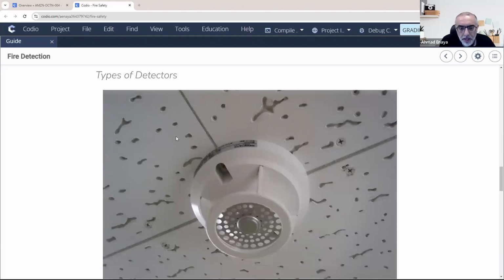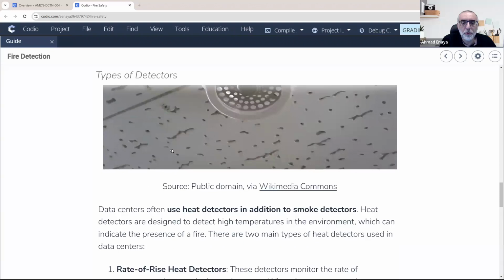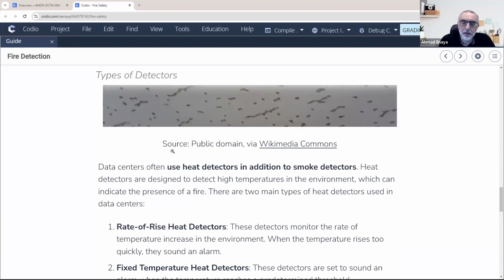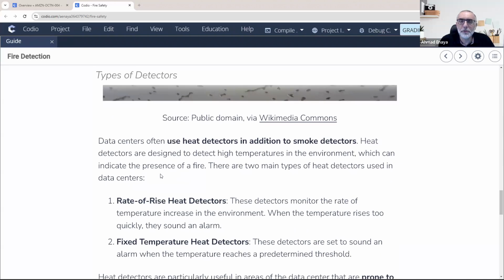Heat detectors will detect heat, as per the name, and they will report to the central unit when the heat exceeds a certain level. Some of them also look at the rate of rise. So some of them will trigger the alarm when the heat is increasing rapidly. Some of them are threshold based, which means they will report the alarm when you exceed a certain temperature. This is called a fixed temperature heat detector because it is based on temperature. The other one is based on change. If there is a rapid change in temperature, then they will report it to the system.